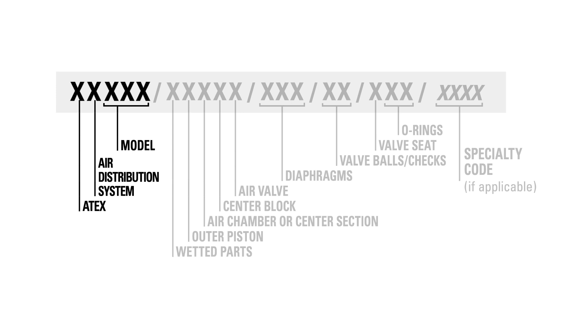The first section identifies the ATEX certification if applicable, as well as the pump's air distribution system and model. The first digit in this section is optional and denotes whether the pump model is ATEX rated. If the pump model's description starts with an X, the pump will be ATEX rated. If it starts with anything else, the pump is not ATEX rated.